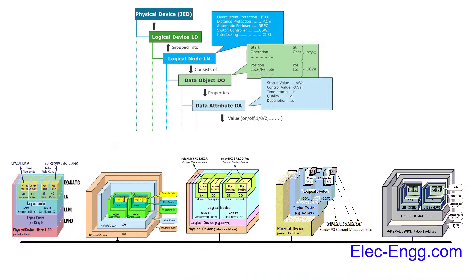The data model of the IEC 61850 standard is an object-oriented one, grouping the data into the smallest possible functions to be implemented independently. These smallest possible functional units are called logical nodes. The logical nodes, data, and attributes contain names according to standardized semantics. In IEC 61850, as you can see, the physical device and logical device names are not standardized and can be selected freely.